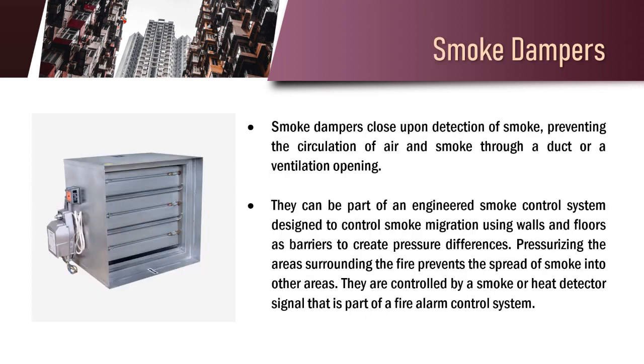Smoke dampers, on the other hand, close upon detection of smoke, preventing the circulation of air and smoke through a duct or a ventilation opening. They can be part of an engineered smoke control system designed to control smoke migration using walls and floors as barriers to create pressure differences. Pressurizing the areas surrounding the fire prevents the spread of smoke into other areas. They are controlled by a smoke or heat detector signal that is part of a fire alarm control system.